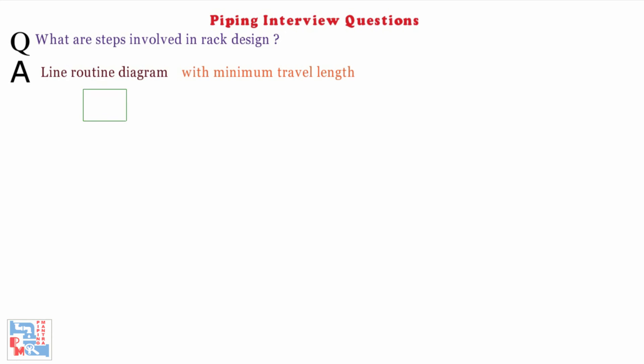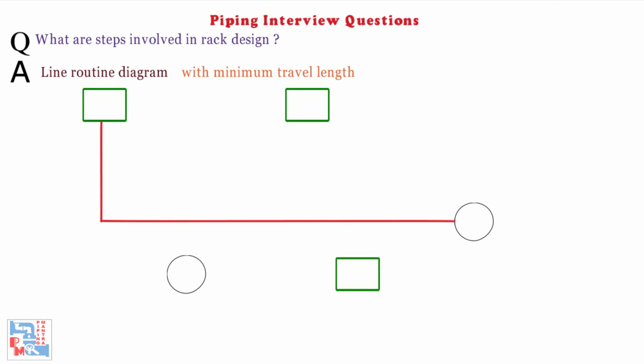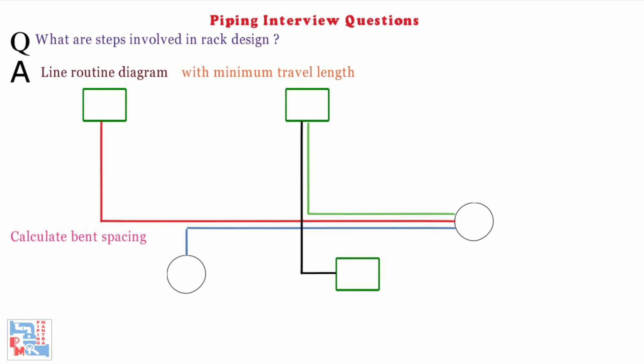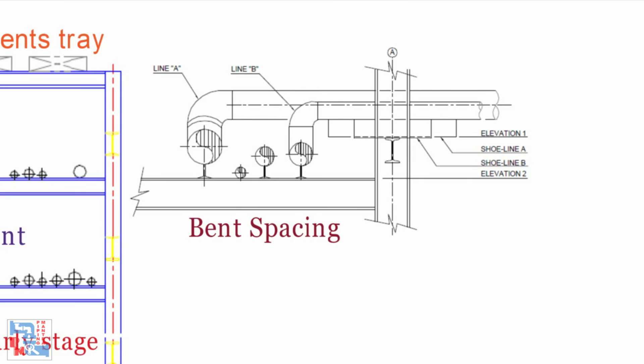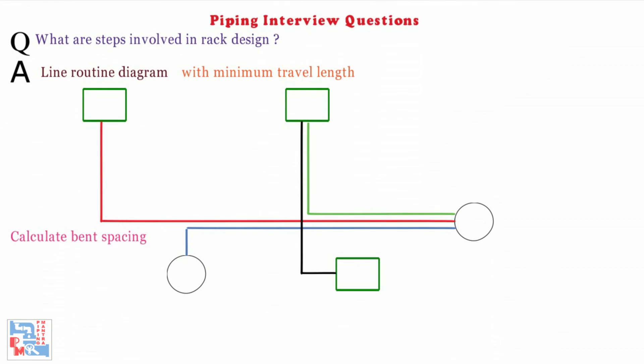Next: What are the steps involved in rack design? First, generate the line routing diagram to find the line origin and destination with minimum travel length based on the process flow diagram and preliminary P&ID. Calculate bent spacing between tier to tier, set rack width, and decide elevations and levels.